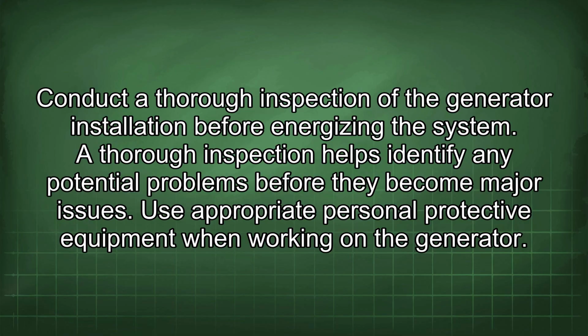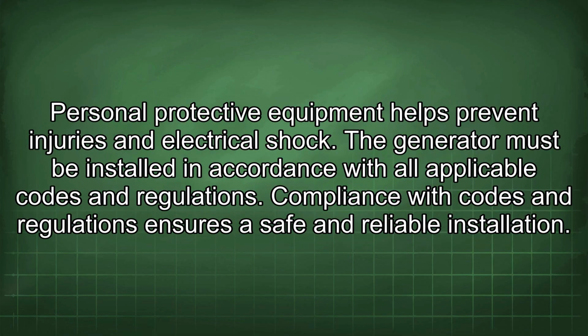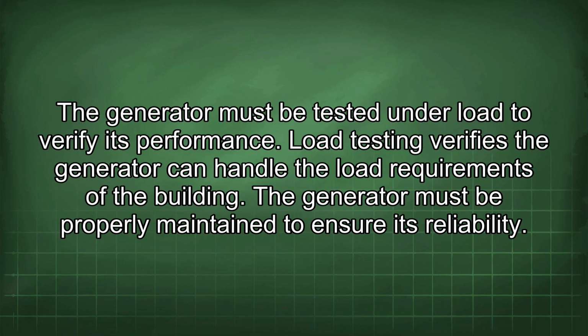Use appropriate personal protective equipment when working on the generator. Personal protective equipment helps prevent injuries and electrical shock. The generator must be installed in accordance with all applicable codes and regulations. Compliance with codes and regulations ensures a safe and reliable installation. The generator must be tested under load to verify its performance. Load testing verifies the generator can handle the load requirements of the building.